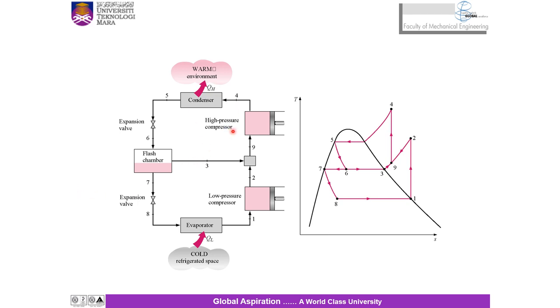When the fluid used throughout the cascade refrigeration system is the same, we don't have a heat exchanger — we use the same refrigerant for the bottom and top cycle. So the heat exchanger can be replaced by a mixing chamber, which we call a flash chamber, because it has better heat transfer characteristics. So you have a two-stage compression refrigeration system shown here in the diagram.